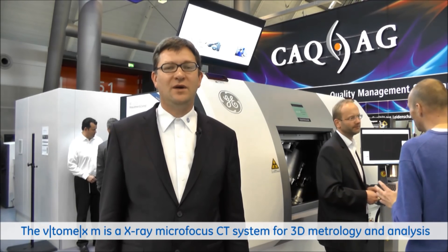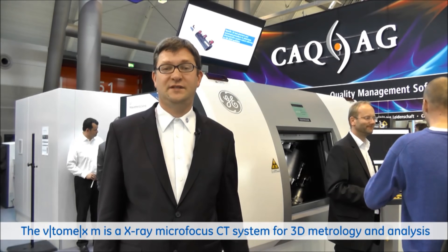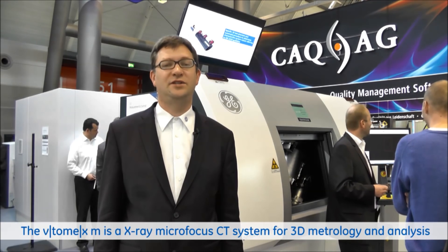The next system I would like to introduce you to is the v|tome|x m Metrology Edition. It combines high-performance 3D imaging with high-precision metrology. It is specified according to VDI 2630 with an accuracy of down to 4 micrometers. It is also the first micro CT system which we offer with ScatterCorrect technology.